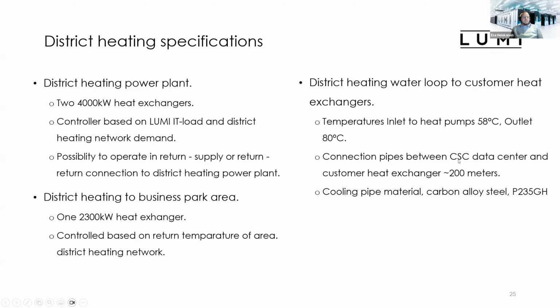And also this business park area, this Renfosiranta business park area, is utilizing this waste heat, and they currently have one 2.3 megawatt heat exchanger installed. And this is only controlled based on the return temperature of the area district heating network. So basically, if the district heating network doesn't have enough demand, we are closing the valve when the return temperature increase is too high.